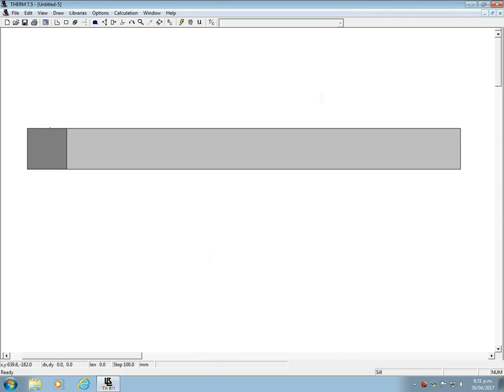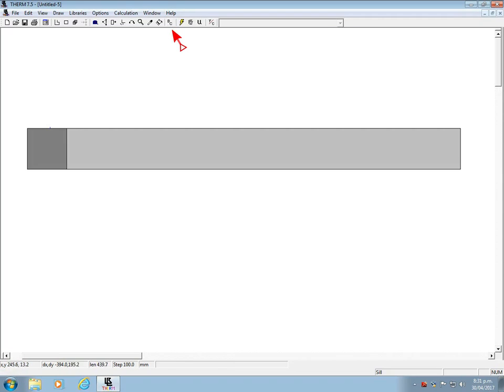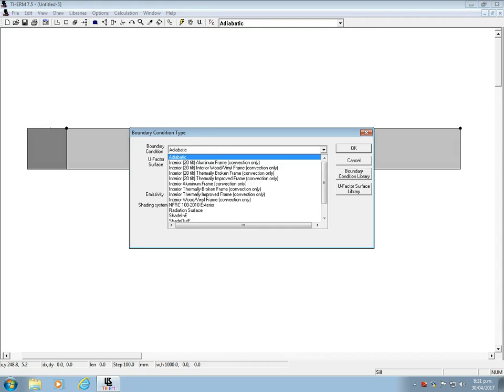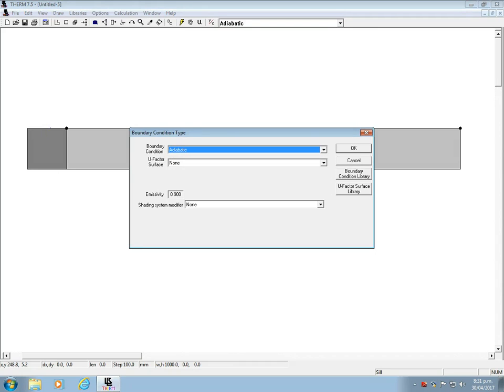So let's assign boundary conditions so that Therm can calculate the heat flow. Click on BC as in boundary conditions. And by default all boundary conditions will be set to adiabatic, which means no heat is flowing and is not what we want. So we need to create some boundary conditions that make more sense. Go to Libraries again, but this time Boundary Condition Library.